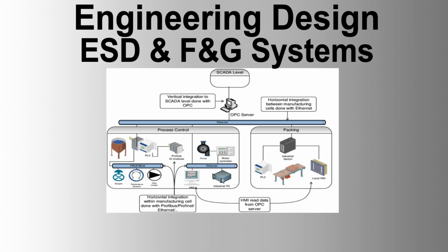Testing. General testing requirements. 1. Factory acceptance testing, FAT. FAT must be conducted to ensure that the ESD F&G system meets all specified requirements before delivery. The FAT procedure should include functional testing, performance testing, and integration testing. Vendor shall supply appropriate hardware and software to simulate PLCs within equipment provided by others, confirming correct data transfer and protocol compatibility of the serial link interfaces.